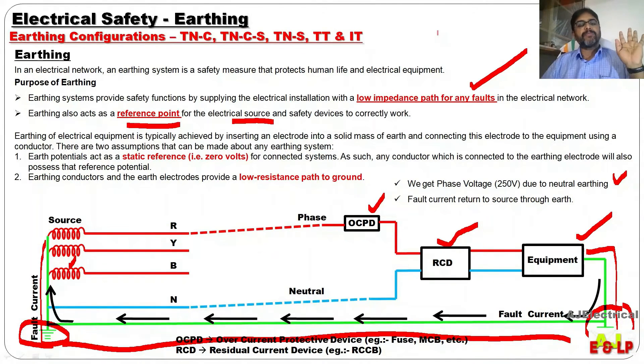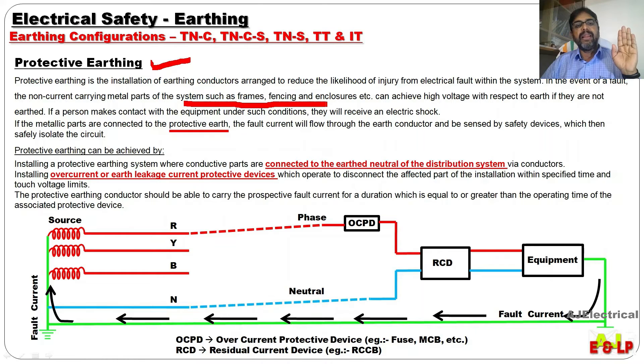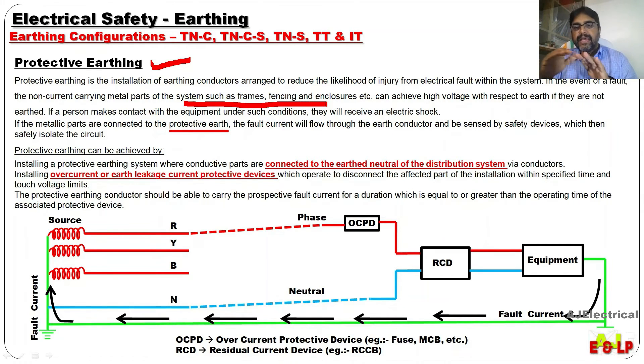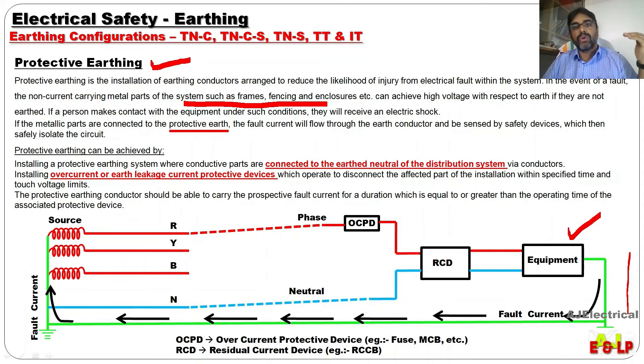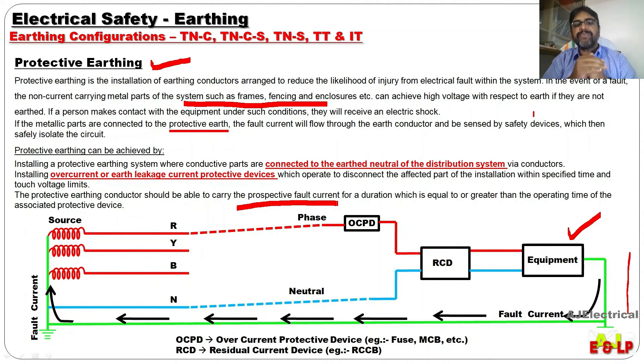I have generally explained about earthing. Now we shall move into protective earthing. For the protection of the human or the equipment, we will earth the frames, fencing, or enclosure — anything related with an installation. That will be earthed. See here, this equipment body is earthed and through the earthing conductor it is getting into contact with the neutral of the source. The fault current will be passing through the earth part. So the earth conductor should be able to carry the fault current up to the duration of tripping of the system or the safety devices — OCPD or RCD. That is about protective earthing.